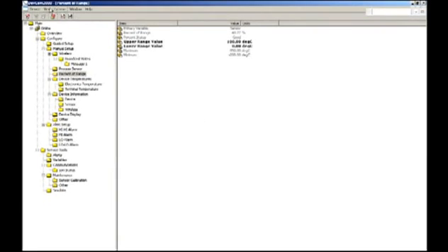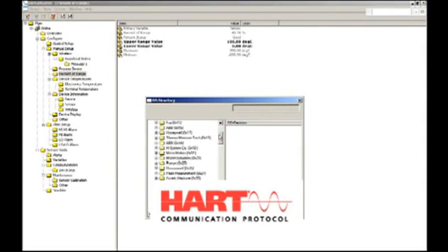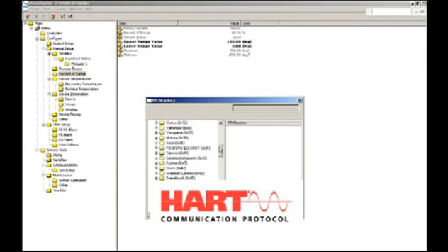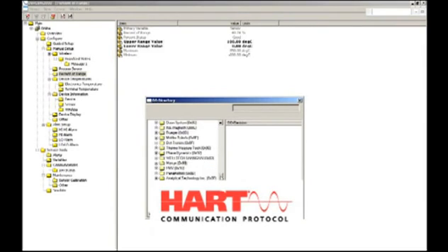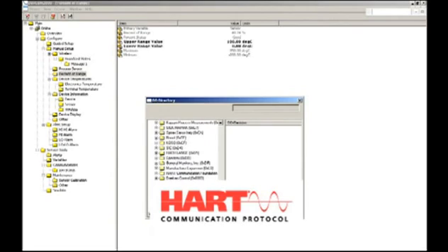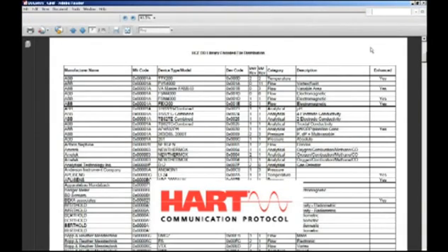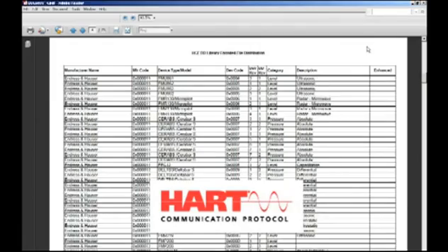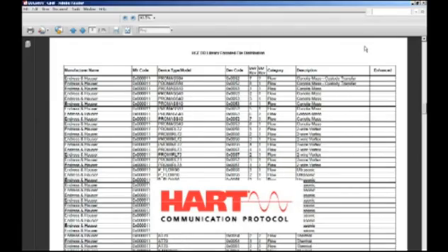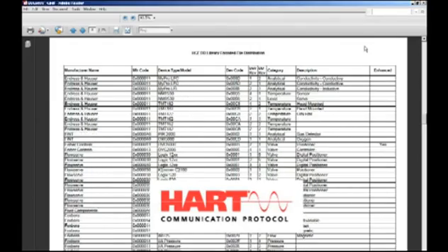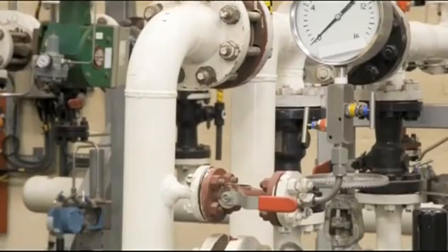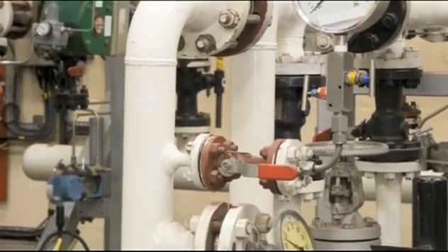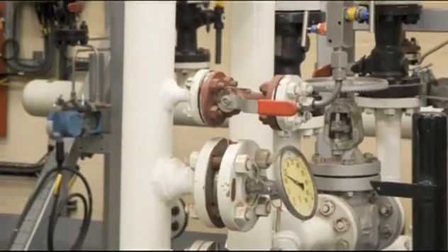Here you see a list of DDs in the DevCom 2000 software. DevCom 2000 uses the compiled device description binary file, the DD developed by the device manufacturer and registered with the HART Communication Foundation. Each DD has been tested by the device manufacturer. This is an important point because, as a result, we know that every DD will work with the device, be it a transmitter or control valve.